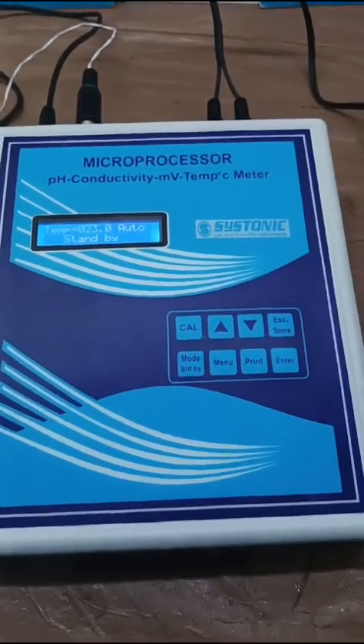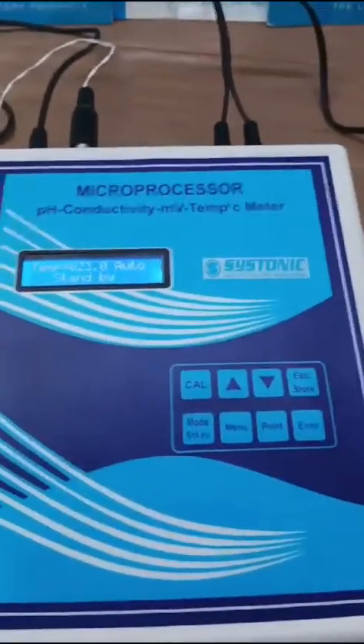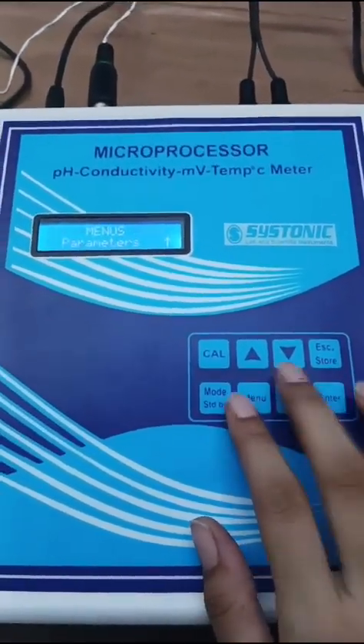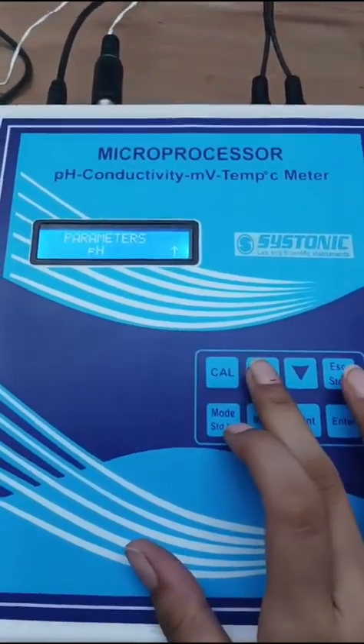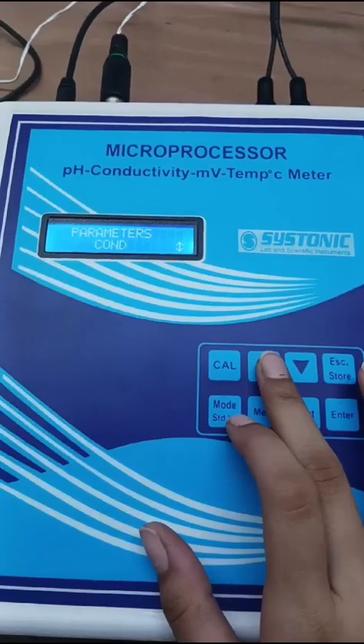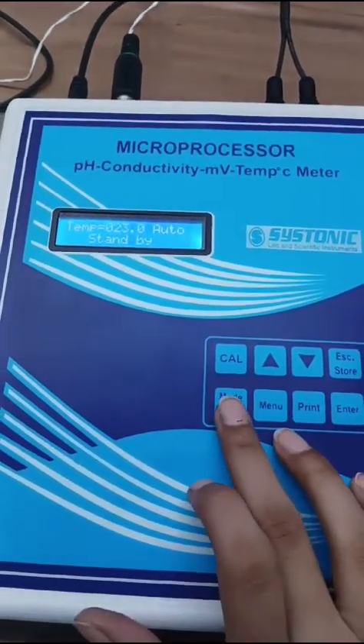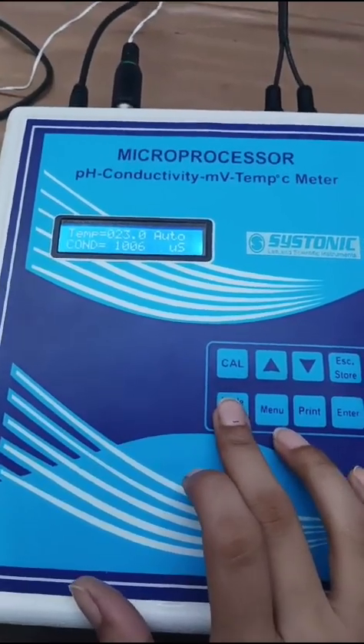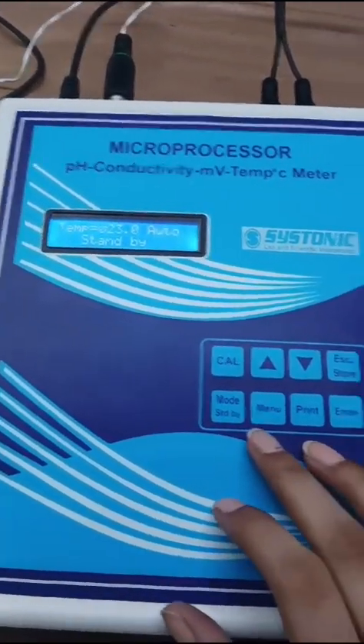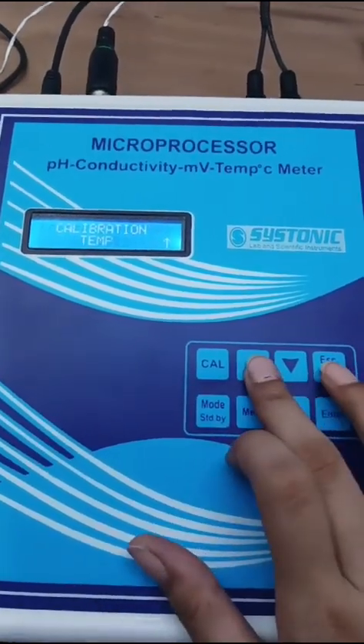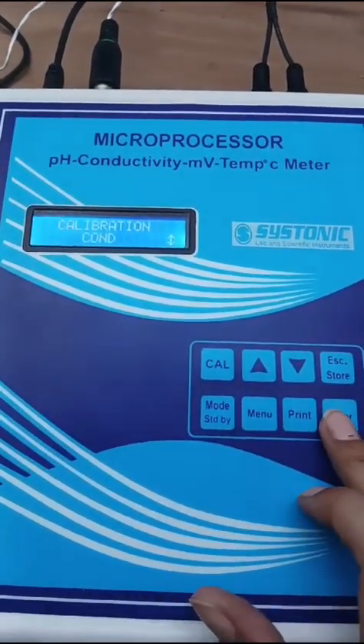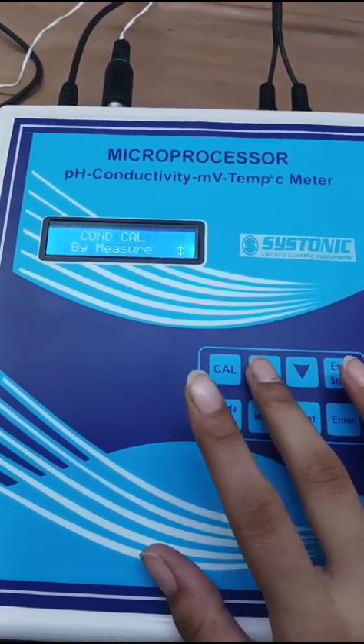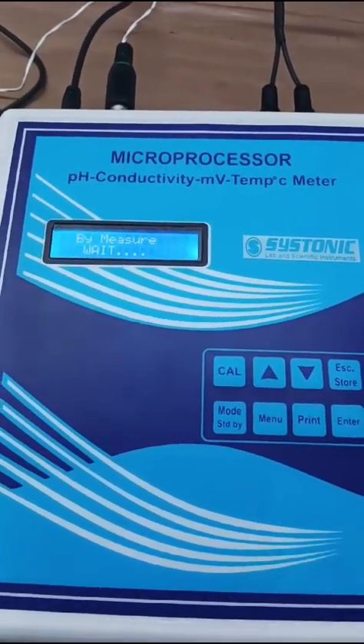So for the conductivity part, as we have connected the cell and dipped it in 1 millisiemens standard solution, as you can see, now to change the parameter, go to menu and from here press enter. You can change the parameter of mode through this and then press enter, and you can see its conductivity now. After that, go to cal and to conductivity, press enter, and now go to by measure, press enter and wait.